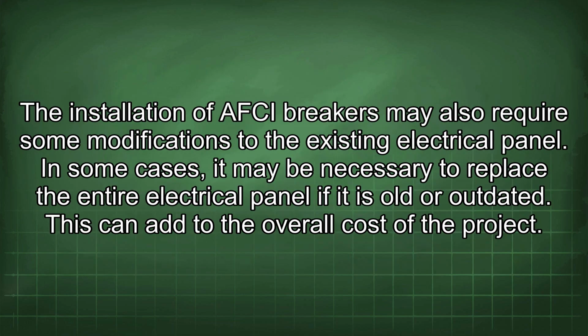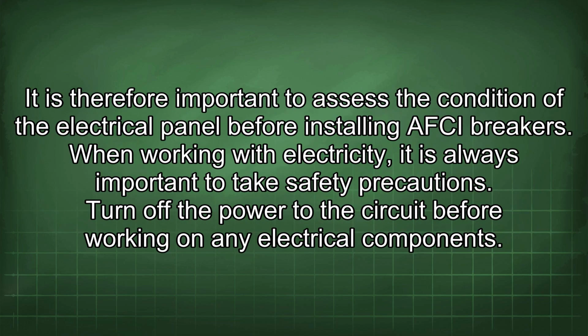The installation of AFCI breakers may also require some modifications to the existing electrical panel. In some cases, it may be necessary to replace the entire electrical panel if it is old or outdated. This can add to the overall cost of the project. It is therefore important to assess the condition of the electrical panel before installing AFCI breakers.